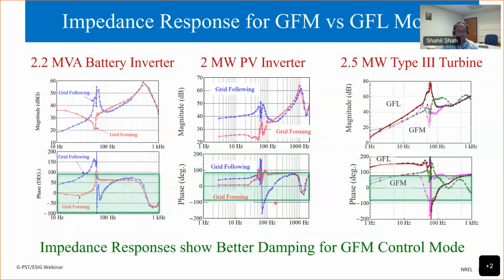So what we get from these impedance responses, one is, as I talked about, that we can understand how IBR is impacting the stability, whether it's a negative contributor or positive contributor. The other application of impedance responses is control design, how to understand what different control modes are going to do. For example, grid forming versus grid following, how they impact the system stability.